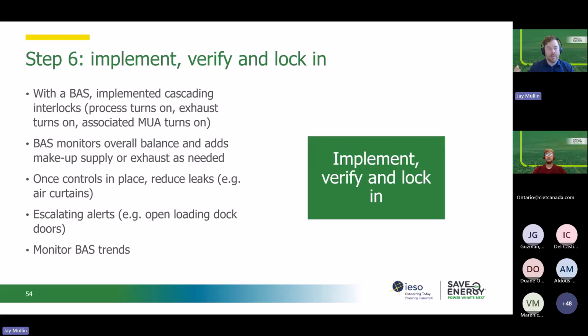So they had those controls in place, which was really helpful in both eliminating the negative pressure situation, but also in terms of energy savings, because limiting how much exhaust they were using and only using that when it was needed meant they could reduce their makeup air overall to only needing to bring in and heat what was needed. And I think he said it was like a 40% reduction in natural gas, just as a result of that. The BAS also monitors the overall pressure balance and adds makeup supply or exhaust as needed.